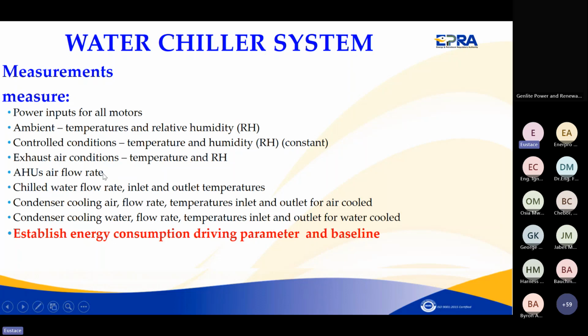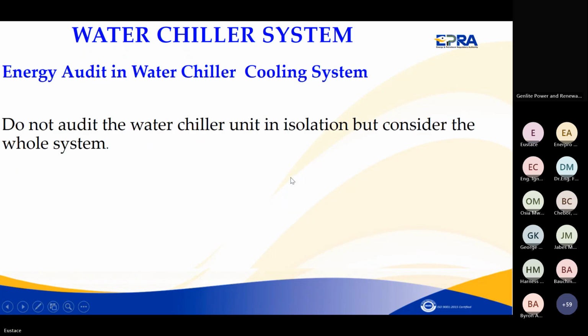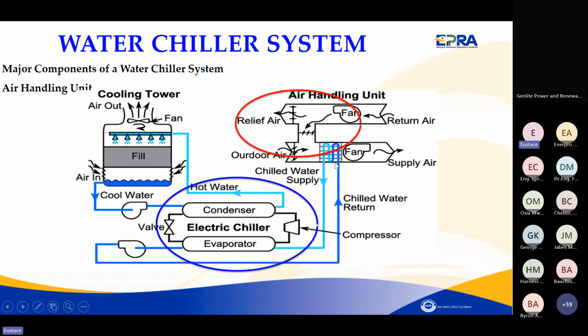You also need to measure the airflow rate, the airflow rates from the air handling units, the water flow rate, and the inlet and outlet temperatures. You can see water going in and out, so you need to measure the water temperatures going to the HVAC system and out. At the same time, you need to log the power of each pump and fan.